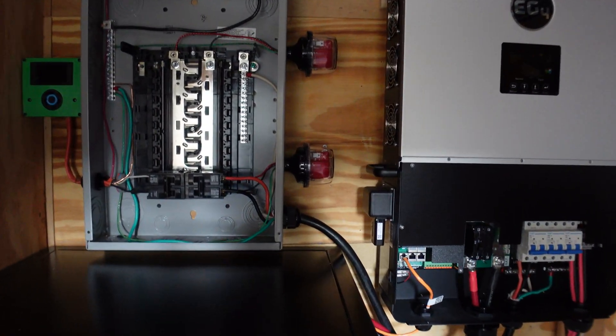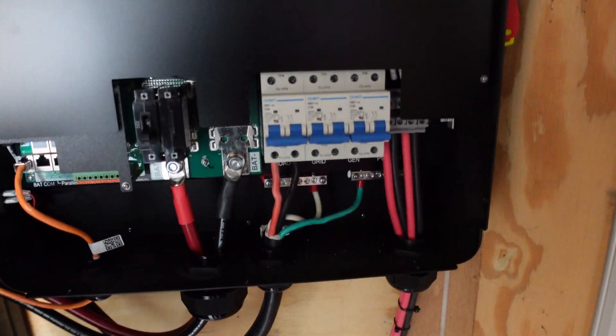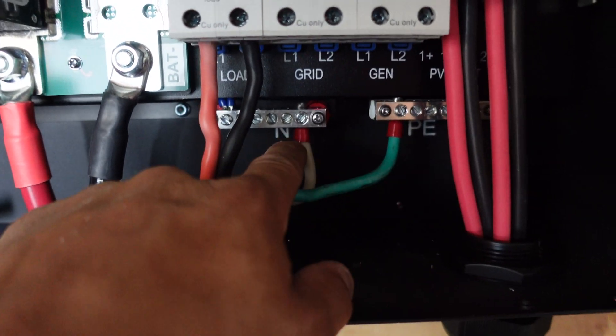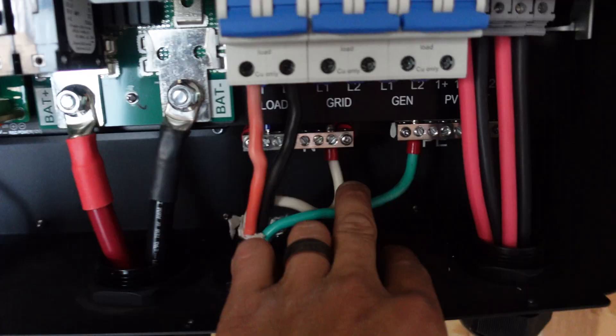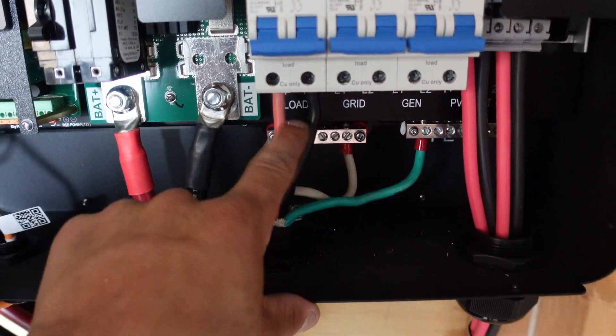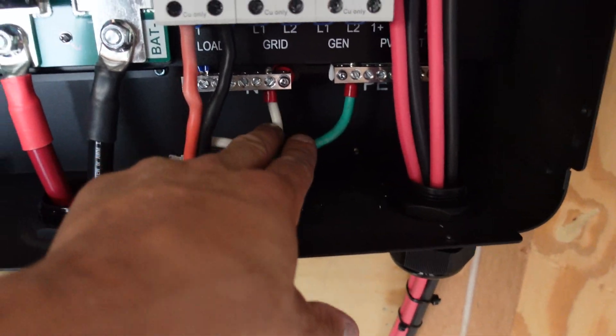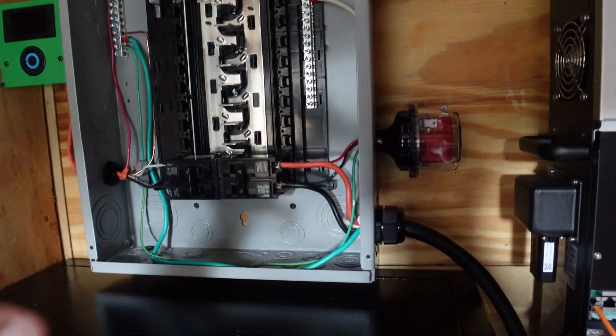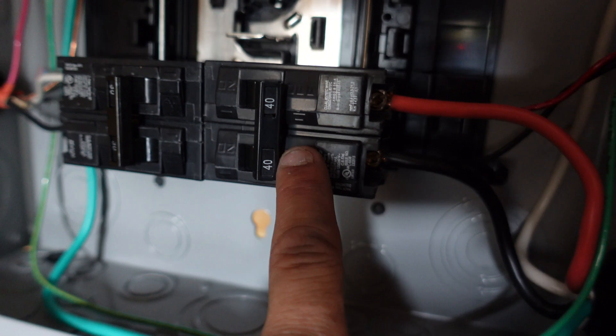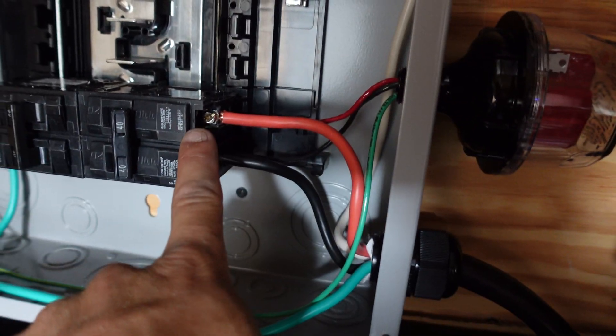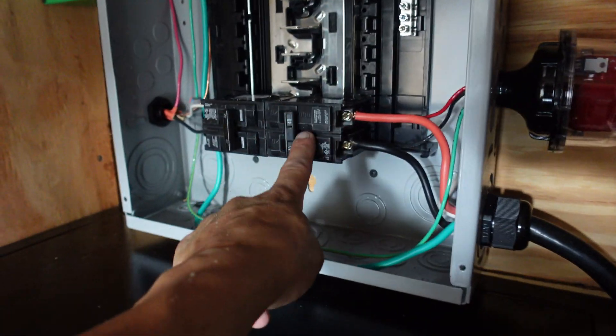So a bit more than a second later, this is literally like three or four hours later. But I got it all wired up and landed. I got the wire cut here, you can see I got the ground grounded to the neutral bar there. And I actually put these, what are they called, ferrules, we got those on the ends of these wires. Now I realized what the wire gauge meant on this, the six plus two. So it was six gauge here and plus two eight gauges. So these are eight gauges and these wires are six gauge. So it's gonna work perfectly for what I need. It's way overkill for this panel, right?